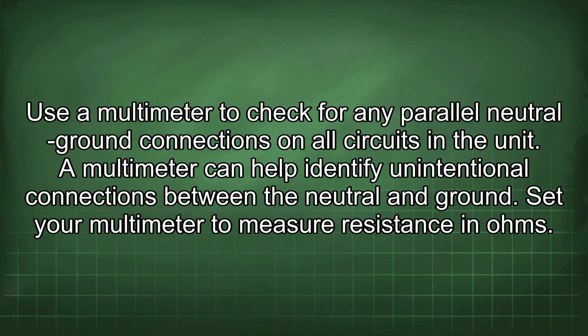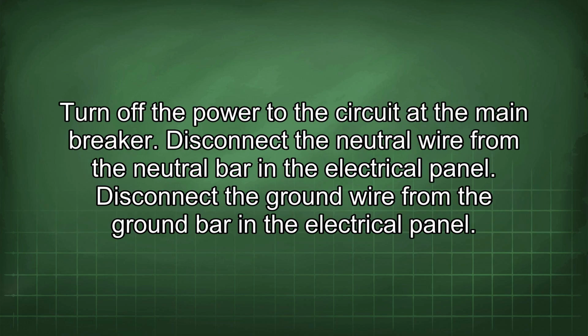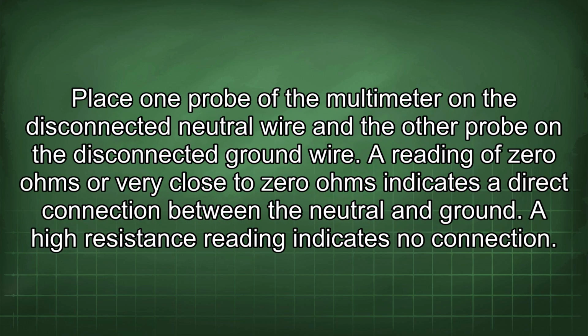Set your multimeter to measure resistance in ohms. Turn off the power to the circuit at the main breaker. Disconnect the neutral wire from the neutral bar in the electrical panel. Disconnect the ground wire from the ground bar in the electrical panel. Place one probe of the multimeter on the disconnected neutral wire and the other probe on the disconnected ground wire.